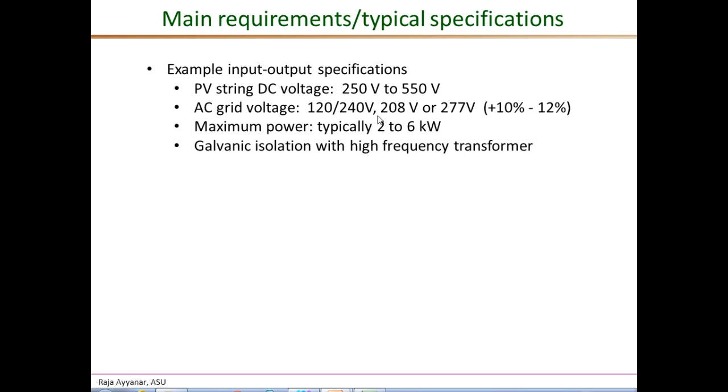Or they can be connected between two phases in a three-phase system, say between A and B, with the line-to-line voltage being 208 volts. Or in a 480 volt three-phase system, they can be connected between the line and neutral, which is 277 volts. A single string inverter should be designed such that it can operate with any of these four AC voltage levels.